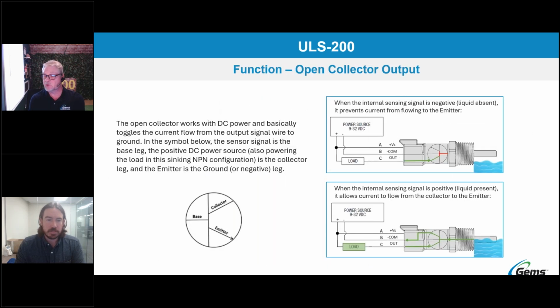I wanted to get into that operating principle a bit further so you know how the insides work. The way it functions is via an open collector output. An open collector works with DC power, and it toggles the current flow from the output signal wire to ground, or to a negative leg, a lower voltage. The sensor signal, in this case the probe, is the base leg. The positive DC power, which is also powering the load because this is a sinking configuration, is the collector leg, and the emitter is the ground or negative leg.